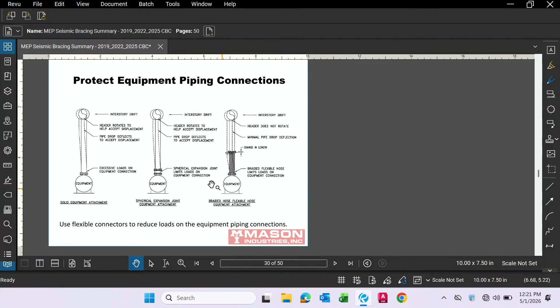This is an illustration of how to handle relative displacement for big equipment. This one has solid equipment attachment - nothing between the piping and the equipment, just solid pipe. So when the building moves, that pipe's going to try to bend, but the pipe's too stiff, putting all that moment at that connection, which is going to rip it.